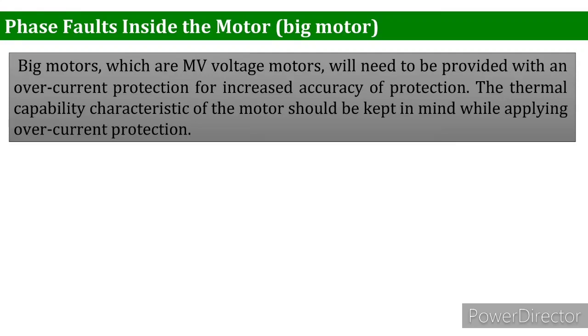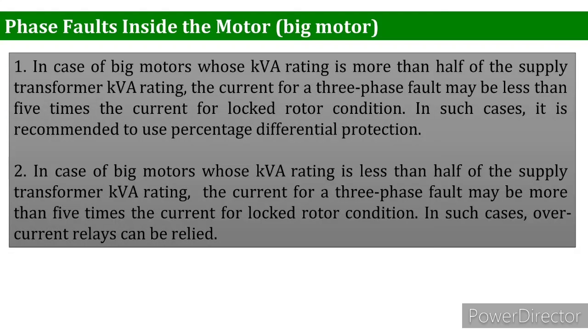Similarly, we have studied the overcurrent relay, so we can also use the overcurrent relay in combination with the thermal capability. This is very important to understand in the case of big motors. In case of big motors, you have two conditions here. In big motors whose KVA rating is more than half of the supply transformer KVA rating, the current for a three-phase fault may be less than five times the current for the locked rotor condition. In such cases, it is recommended to use percentage differential protection, which we have studied in detail in our lecture on the differential protection scheme.